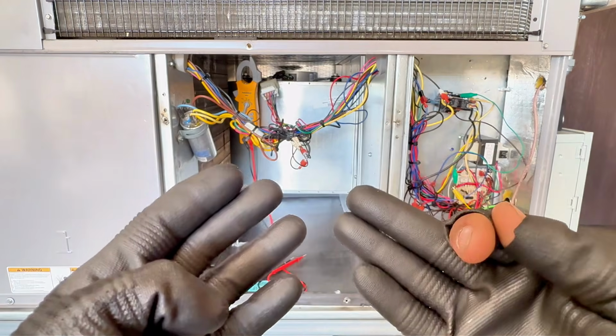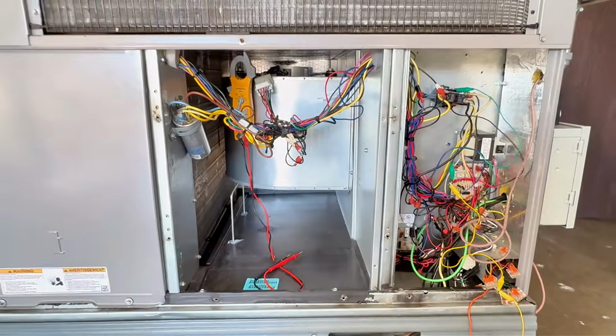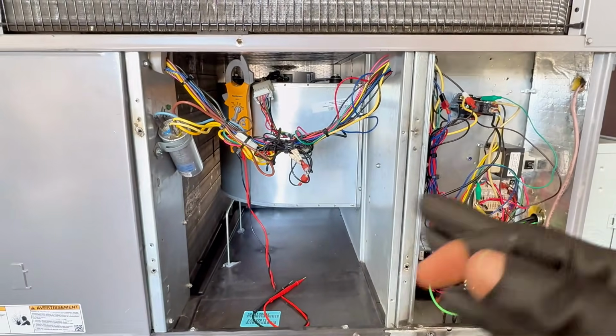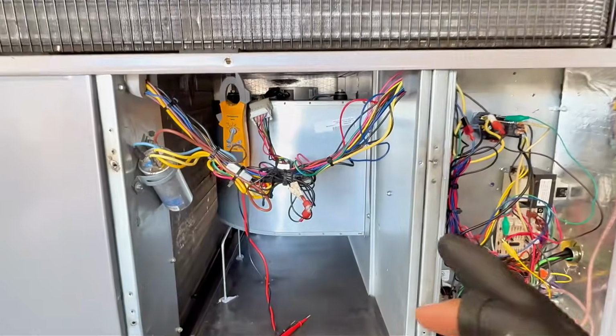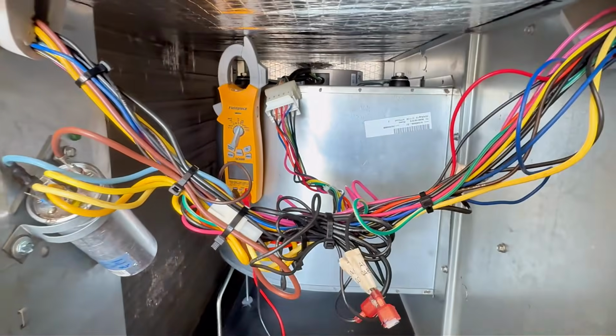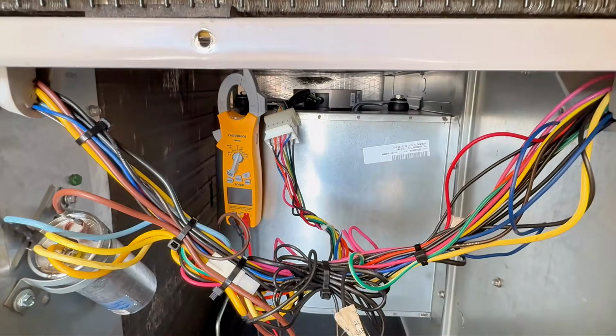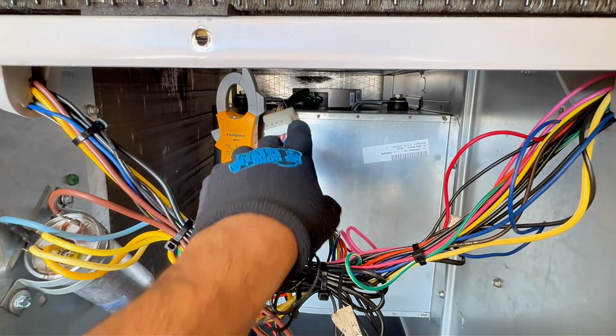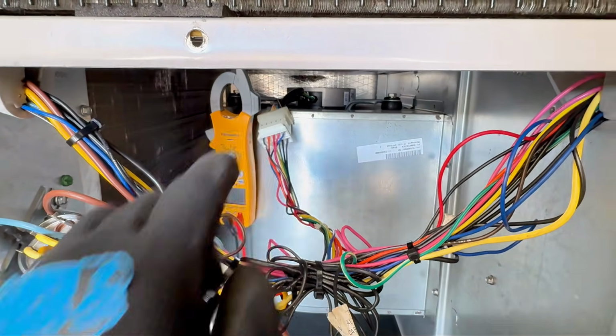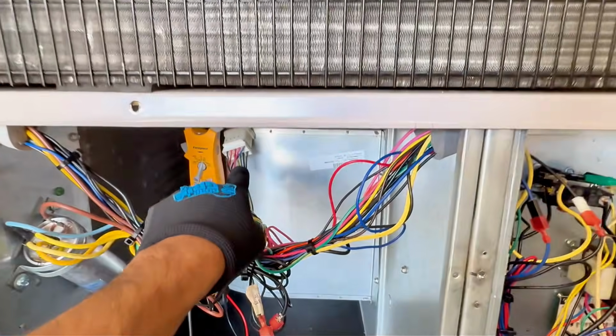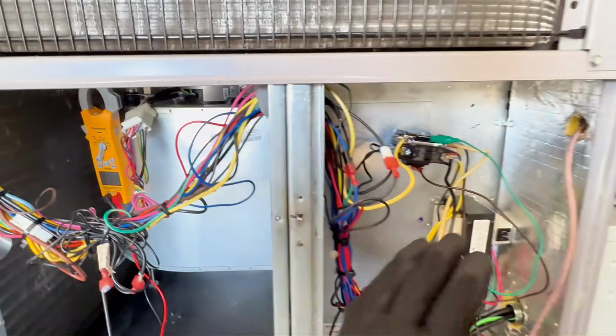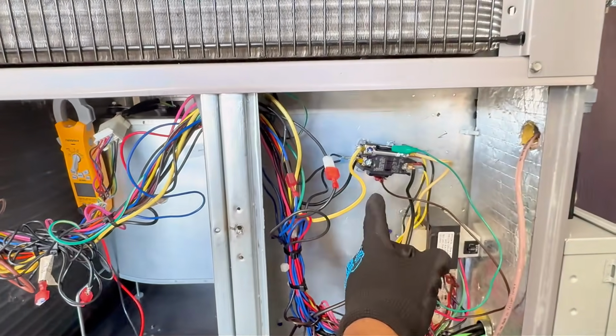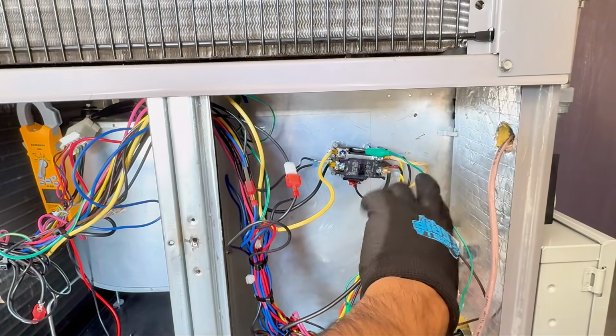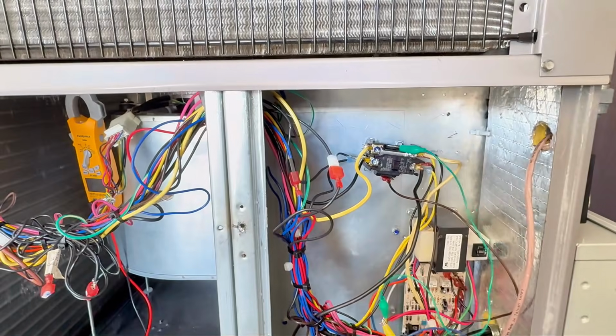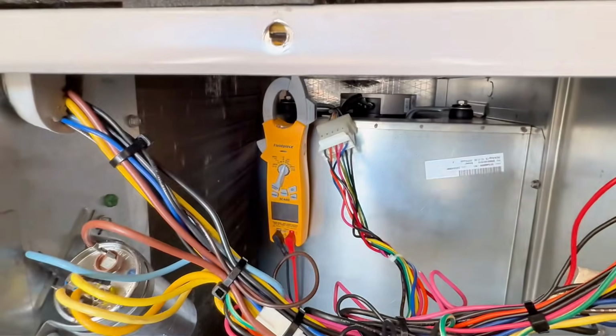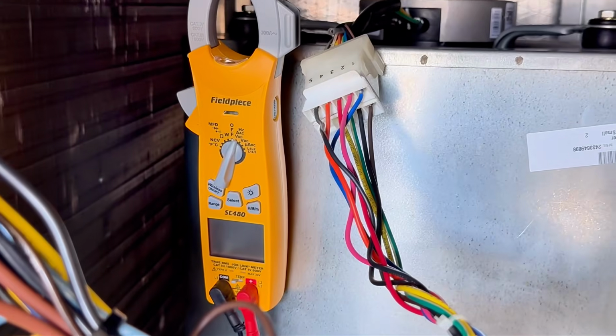So we're gonna check voltage. I am gonna use the tripod mount here, but in the other ones, I might use a neck mount, just a heads up. But with an ECM motor, you have a plug right here. So I'm gonna show you how to check it right here. If you were to check it over here, you would have to follow the wires and see where they go to. So your high voltage typically goes on this side where you have high voltage present all the time, and then your low voltage goes to the board. But I'm gonna go ahead and show you how to check it right here, okay?